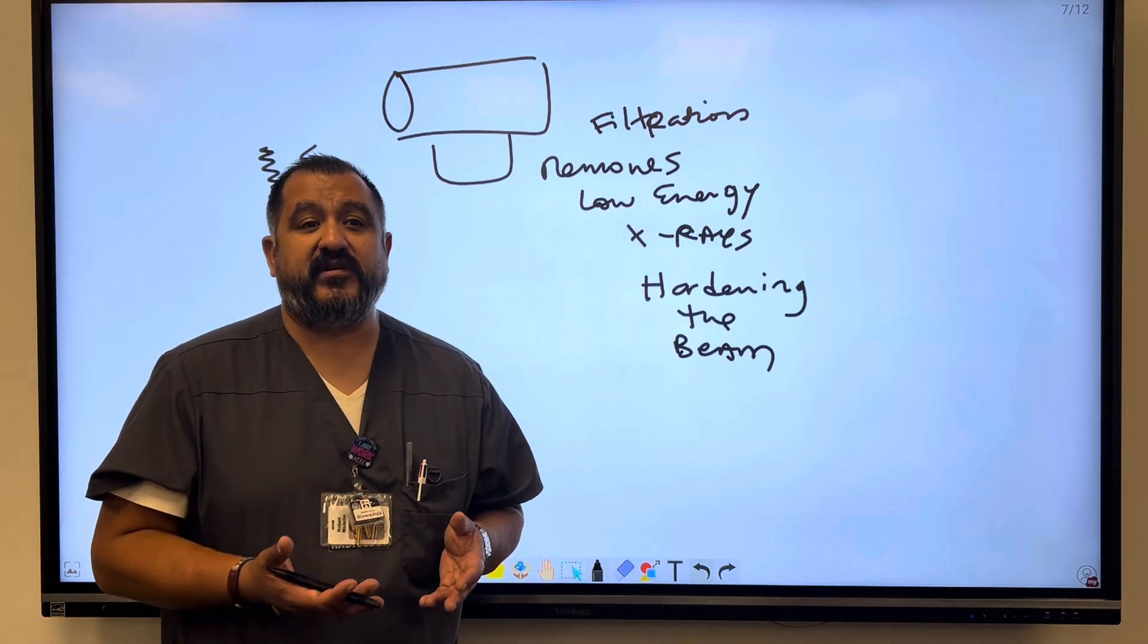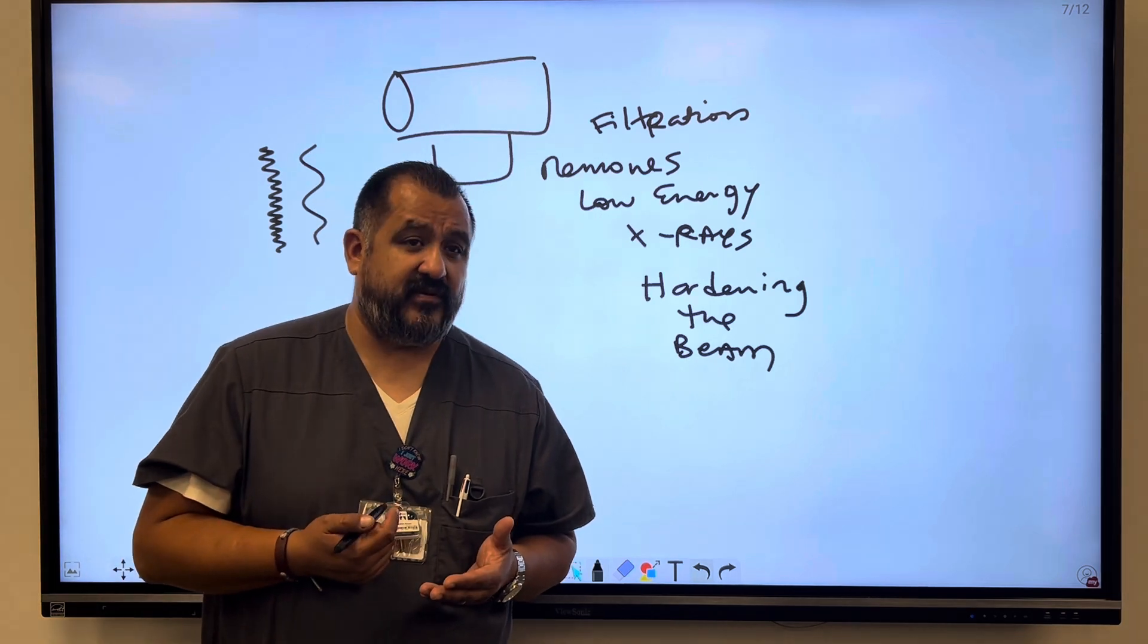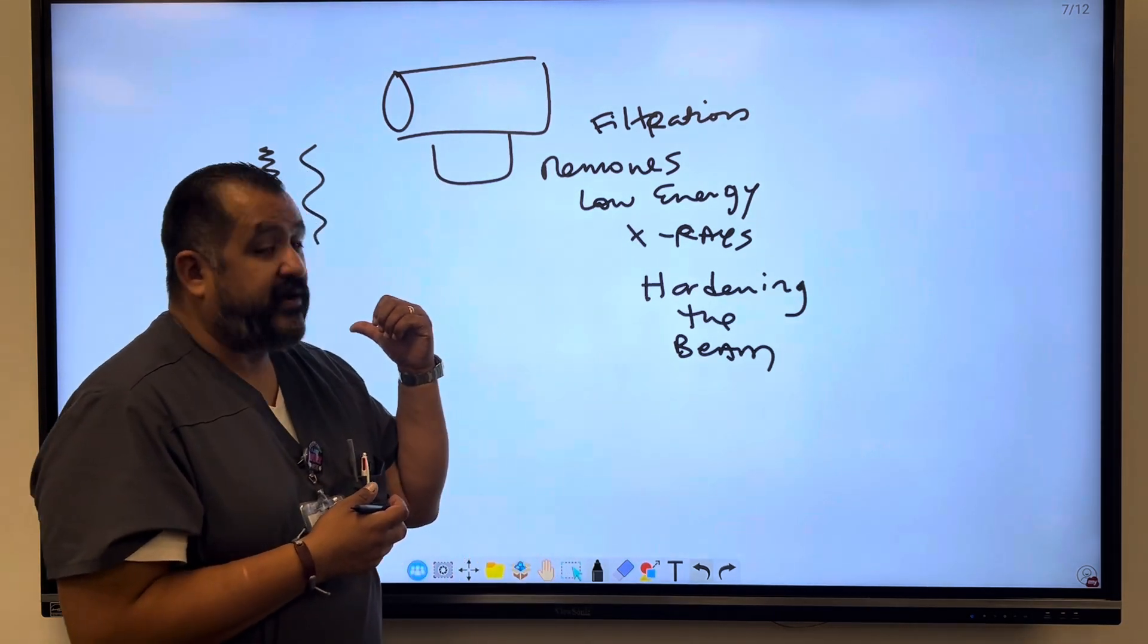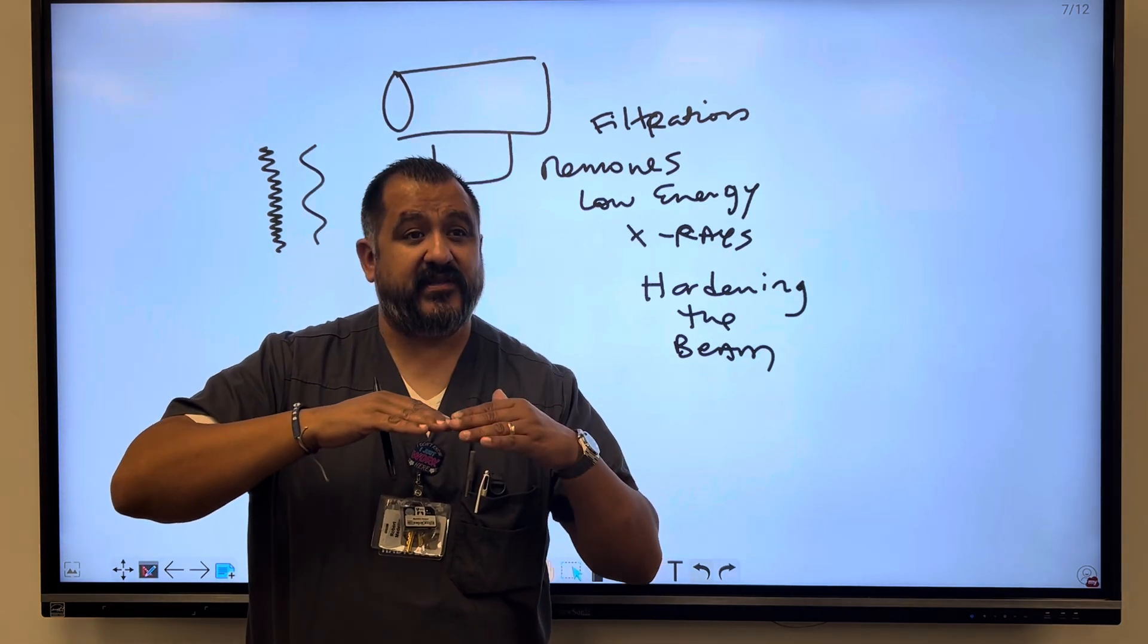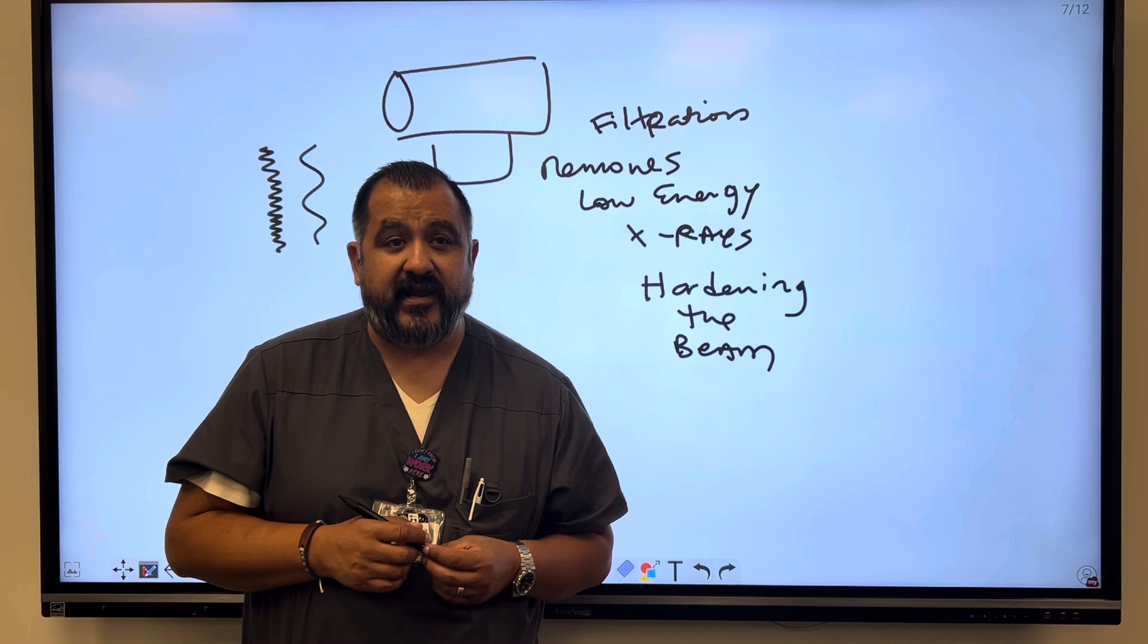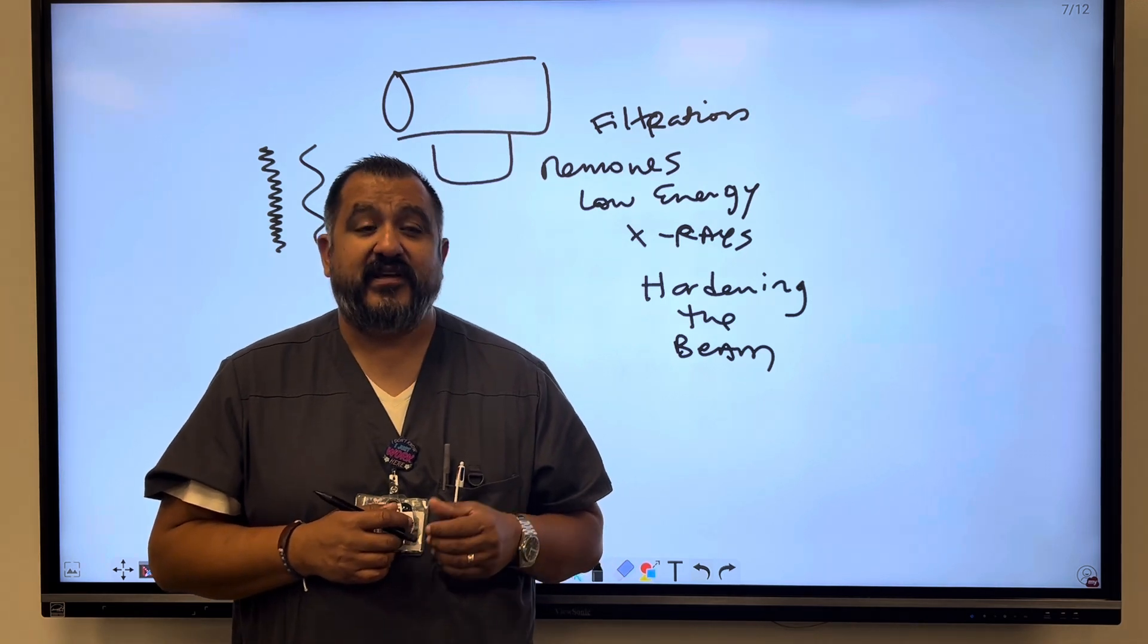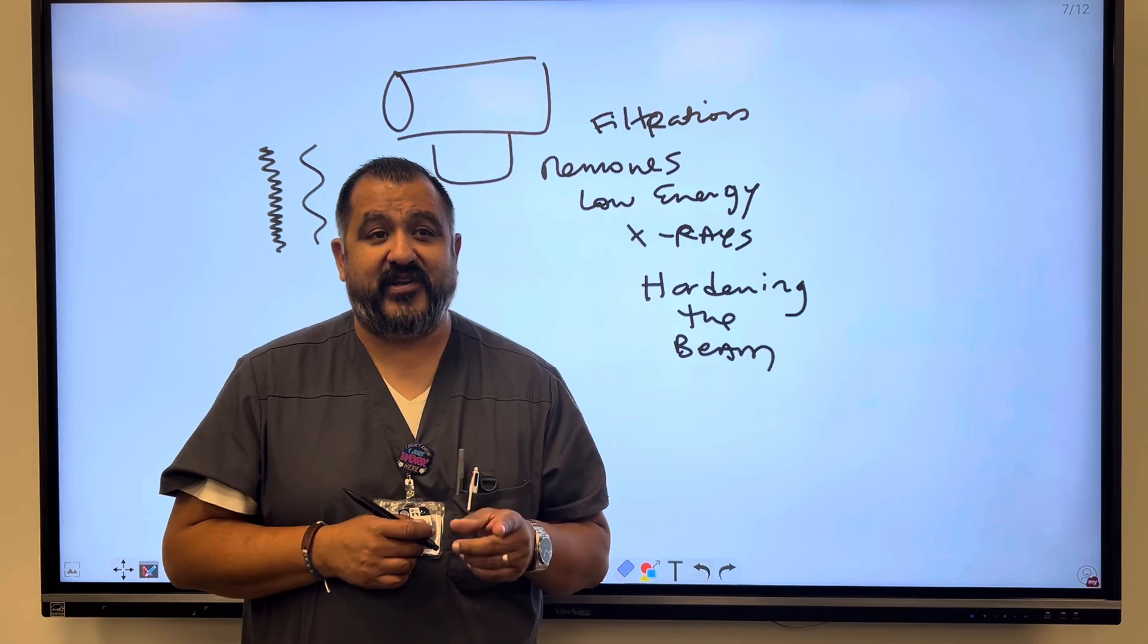So filtration is removing the lower energies before they actually strike the patient. So again, filtration is designed to get rid of the energies that are not useful. So previously, we just said filtration is used to even out the x-ray beam - that's for compensating filters. But when you go back to inherent and added and total filtration, it is designed to remove the low energies before they strike the patient. I want to make sure I add that today.